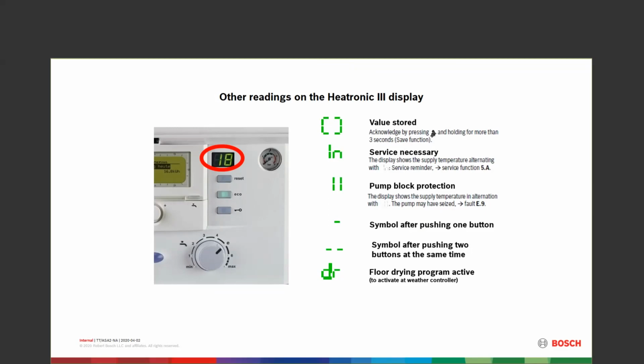And then the floor drying program was designed as a way to get in, using that FW200 control, to do radiant floor drying and get radiant floors set up for it. Most of the time in this country, we don't have a boiler installed when we actually have the floor poured. Usually the boiler comes after. So it's usually in the US a non-event. We don't see it happening very often.